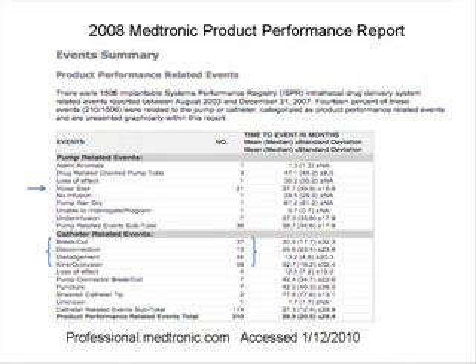So you can see probably from this report that the most common pump-related event is a motor stall. Still relatively infrequent if you look at the total numbers of 1,506 events reported, with 21 having a motor stall. Fairly rare and infrequent. And there are catheter-related events which are a little more common than pump-related problems, where there can be a cut or a small break in the catheter that develops, or a disconnection of the system, or a dislodgement of the catheter, or the catheter actually kinking and occluding upon itself. Again, the numbers are relatively low, but you need to be aware that that is a potential complication.